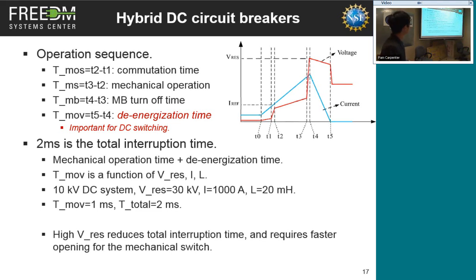We take an example here. Let's say we have a 10 kilovolt DC system, and the residual voltage of the MOV is 30 kilovolts, and you want to turn off 1,000 amps, with a total system inductance of 20 millihenry. By calculation, this period of time is 1 millisecond. Then consider we have a 1 millisecond mechanical switch. That will be 2 milliseconds. So that's the total time.